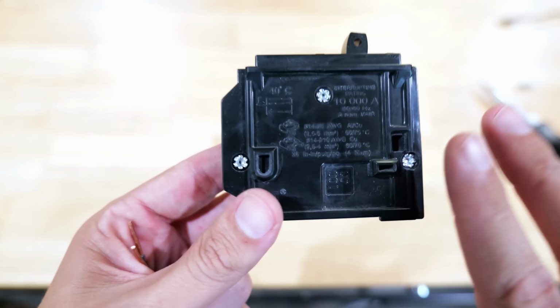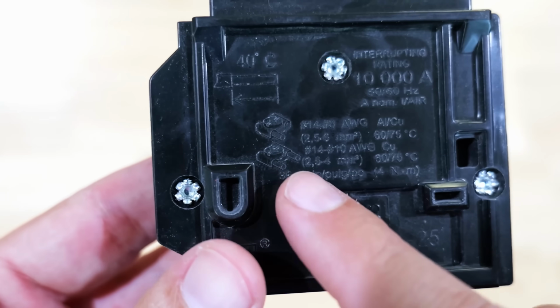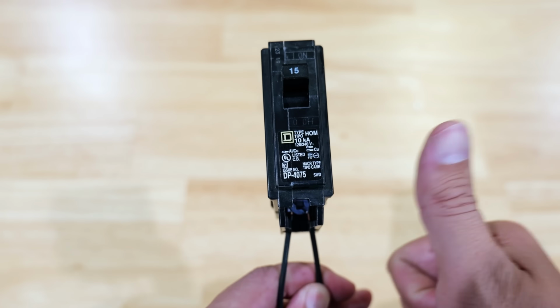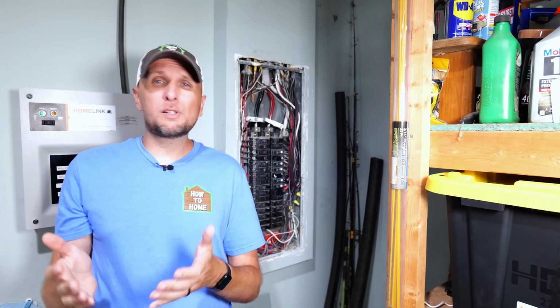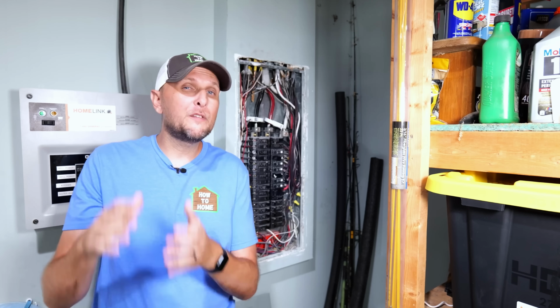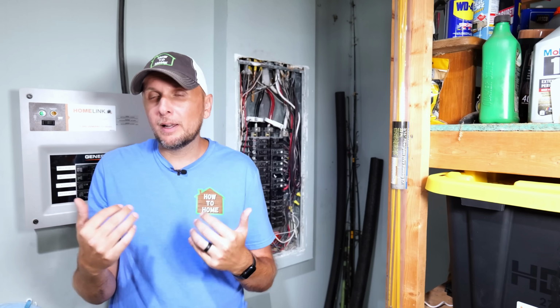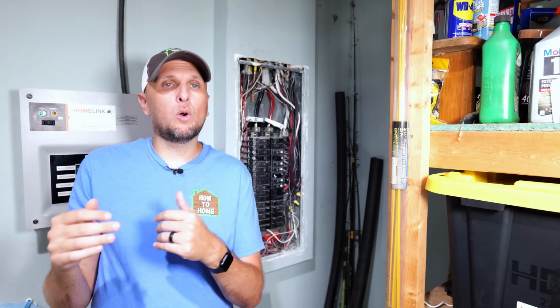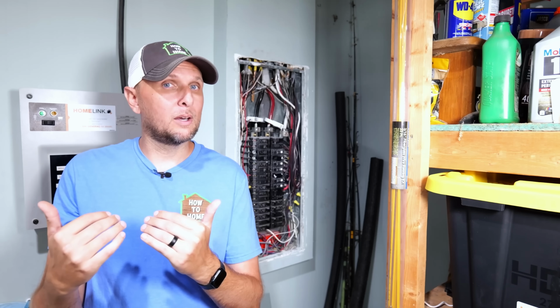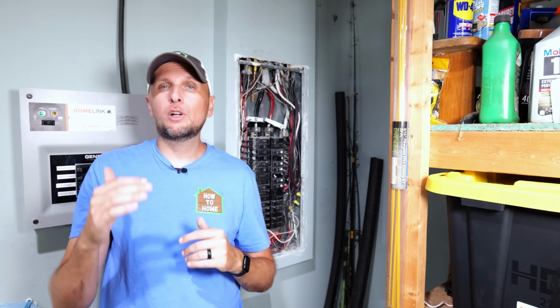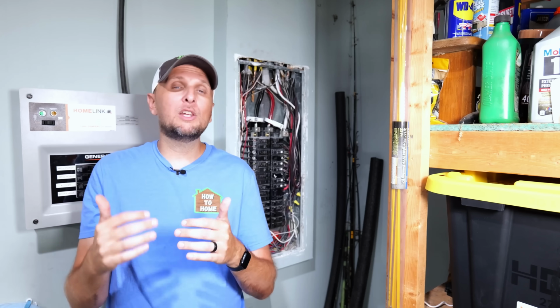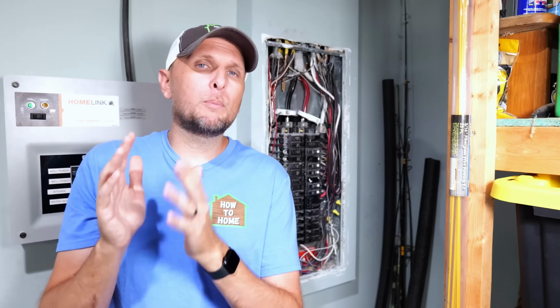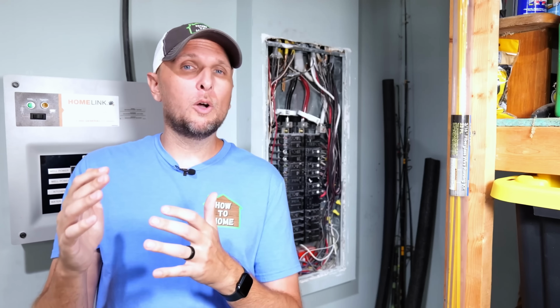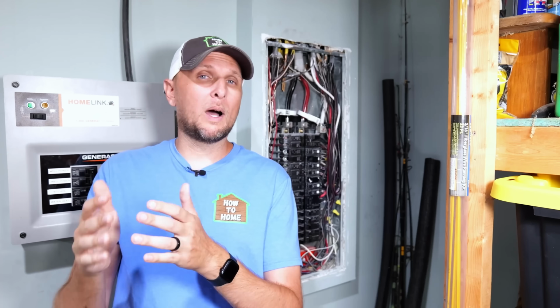What is the fix for this? Well, it's to check the breaker's label, because some breakers like Square D will allow for there to be more than one wire or two wires on a single breaker. But others like Eaton, for instance, they don't. So if you need more circuits, use a tandem breaker. Again, you need to be careful not to overfill or max out your panel. Or again, the safer option would be to install a sub panel. But no matter what you're doing, always make sure to follow the manufacturer's specs, and this way you will avoid problems. Verify what your breaker is and what it can handle, and don't overload breakers that are not designed to have more than one wire attached to them.